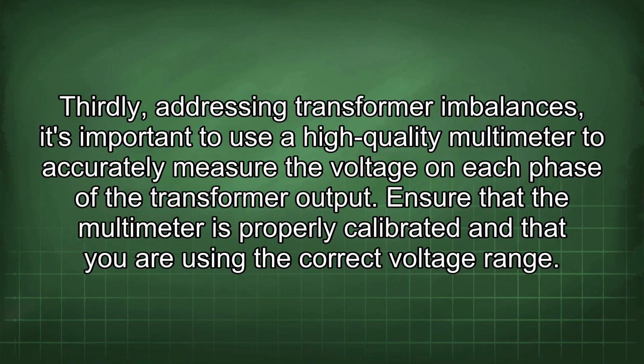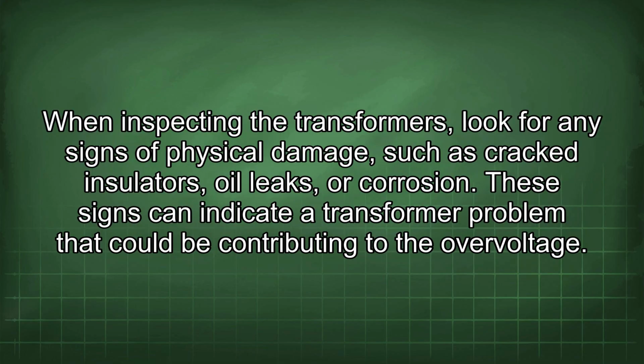It's important to use a high-quality multimeter to accurately measure the voltage on each phase of the transformer output. Ensure that the multimeter is properly calibrated and that you are using the correct voltage range. When inspecting the transformers, look for any signs of physical damage, such as cracked insulators, oil leaks, or corrosion. These signs can indicate a transformer problem that could be contributing to the overvoltage.